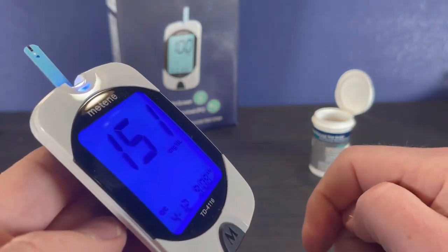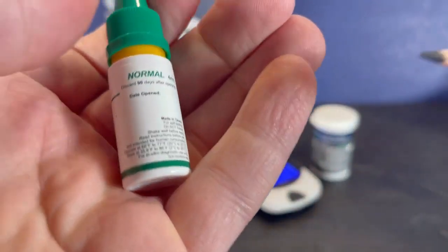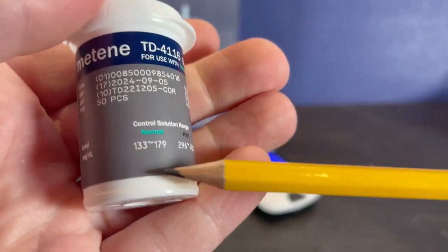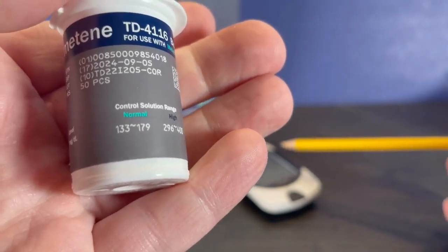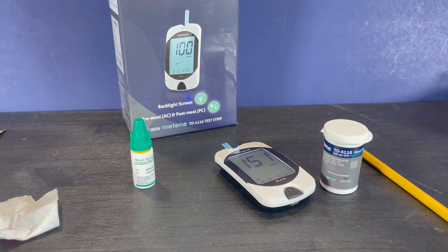The meter shows 151. To read that result, first determine which control solution you have — this is the normal control solution. Get the bottle of test strips you used: the normal range should be between 133 and 179, so 151 is right in the middle. Our meter is reading properly. Let me know if you have any questions about running a control solution test with the Metene blood glucose monitoring system. Please like this video and subscribe to my channel.